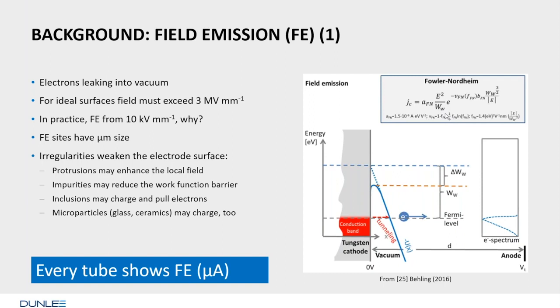Some have microamps, some have 100 microamps, but there's always field emission. There are always weak spots in an X-ray tube. Theory tells us that such an electric field can pull electrons out of ideal surfaces, but theory says we would need 3 megavolts per millimeter to pull an electron out. So it's impossible. We don't have this. We experience field emission already at 10 kV per millimeter. Why is that? That's orders of magnitude lower.